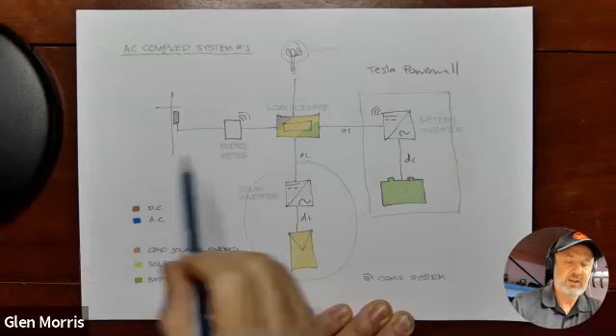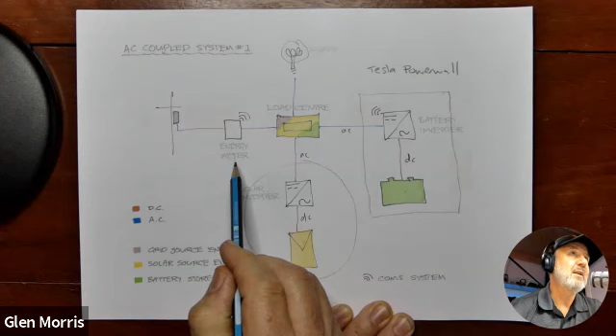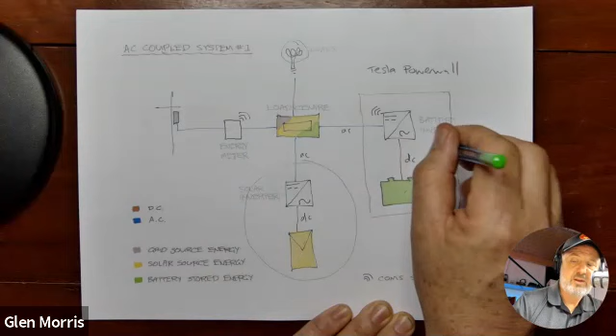Or what brand the battery inverter is. They don't actually need to directly communicate with each other for it to work. But what they do need is some way of measuring the flow of energy. And that's what this here is. Now, this is not your utility meter. This is an upstream meter that's usually provided with the AC coupled inverter.